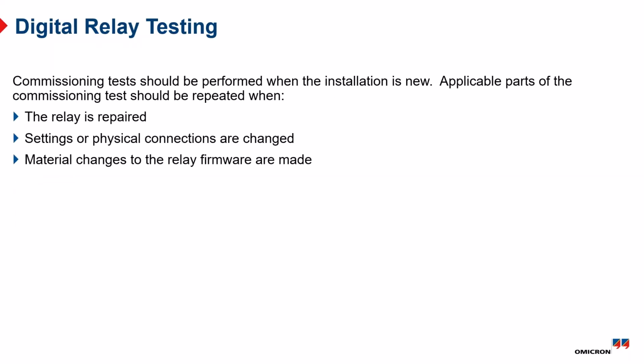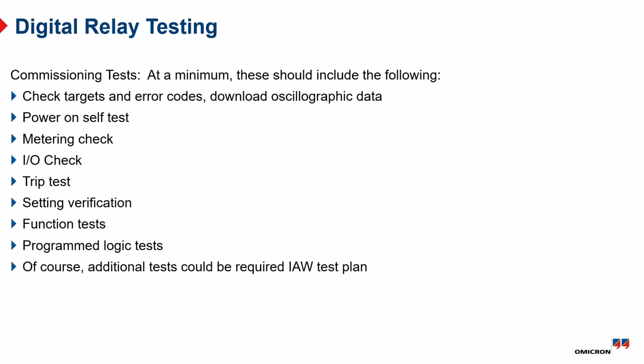Commissioning tests really should be repeated when the relay is repaired, or when you change the physical connections, or material changes to the firmware are made. And like everything else, like your laptop and phone and whatever, these relays, the more complicated they get and the more interconnected they get, the more frequent these firmware patches will have to be made. Commissioning test, of course, is a bit more complex: all of the previous maintenance tests plus functional testing, which can be quite complex.